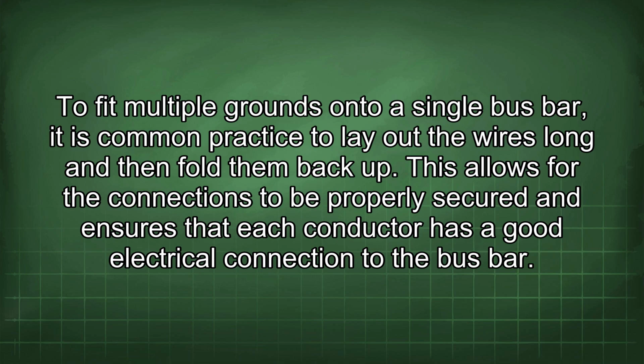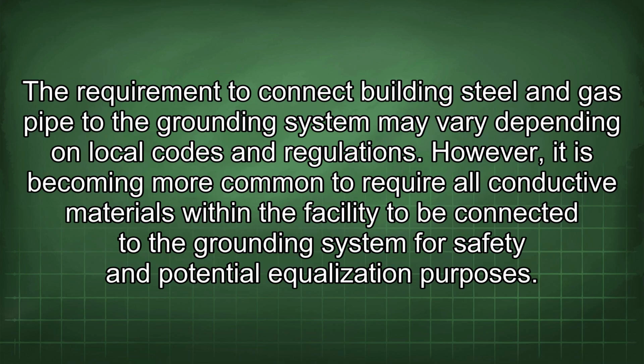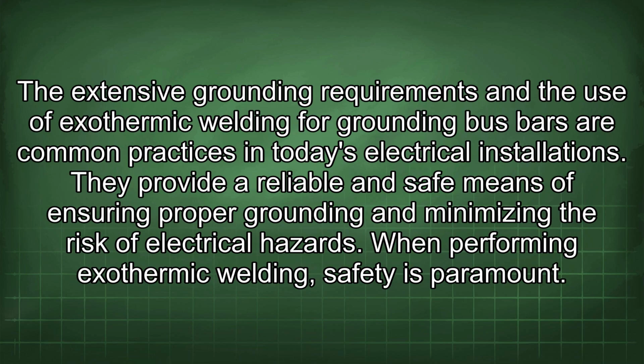The requirement to connect building steel and gas pipe to the grounding system may vary depending on local codes and regulations. However, it is becoming more common to require all conductive materials within the facility to be connected to the grounding system for safety and potential equalization purposes. The extensive grounding requirements and the use of exothermic welding for grounding bus bars are common practices in today's electrical installations. They provide a reliable and safe means of ensuring proper grounding and minimizing the risk of electrical hazards.